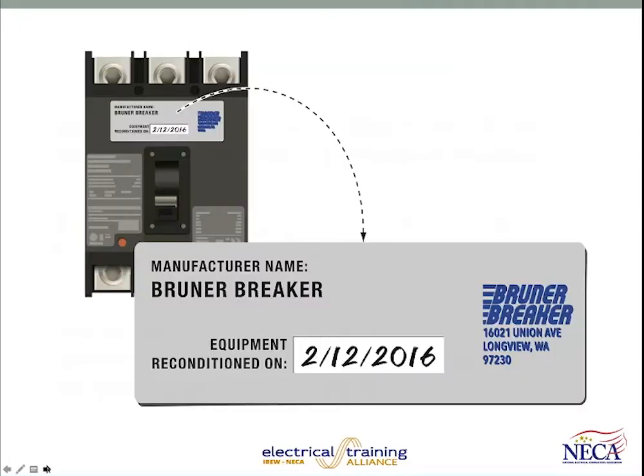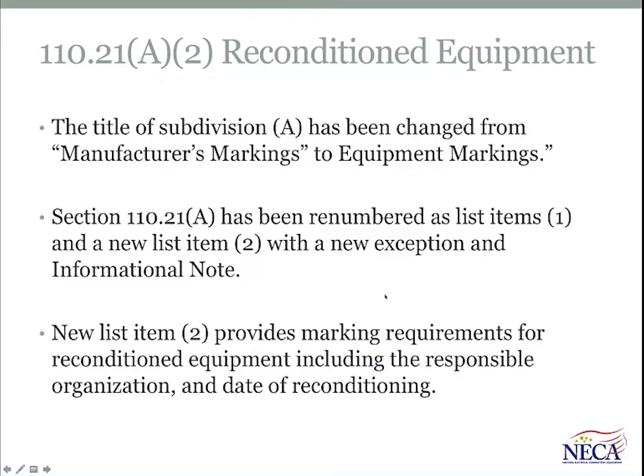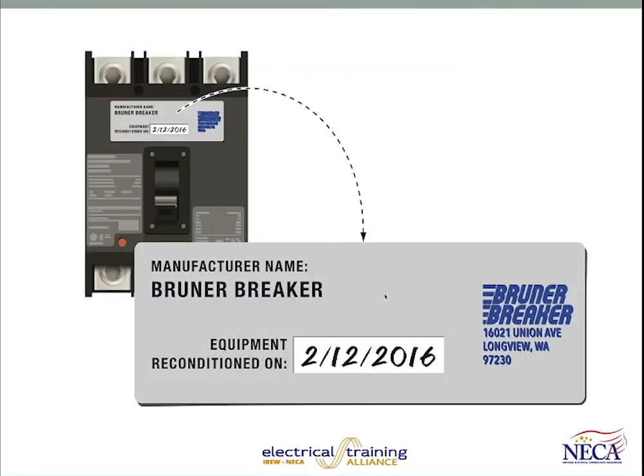We've got a graphic that shows what we're talking about here. For example, if this circuit breaker were built to an appropriate standard and it was remanufactured, it would obviously have to be remanufactured in accordance with the provisions in the applicable product standard. And then the name of the remanufacturing company, oftentimes it's a manufacturer of that equipment, the date it was reconditioned, and the organization's name that was responsible for it. So a new labeling requirement there for remanufactured equipment.